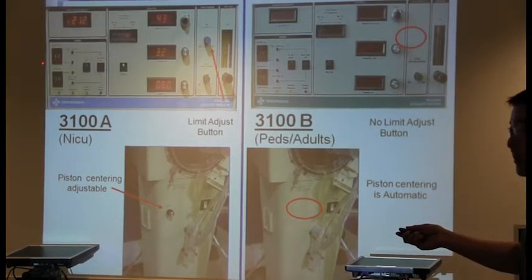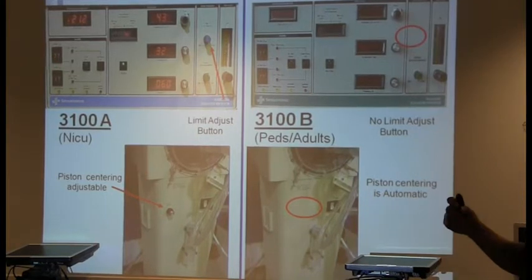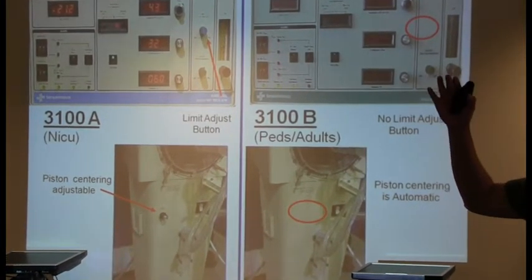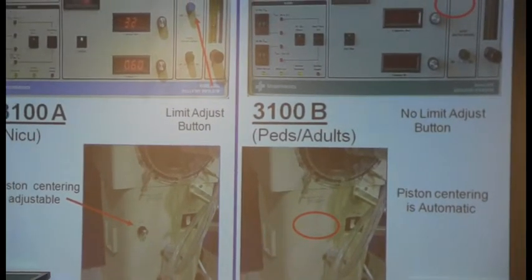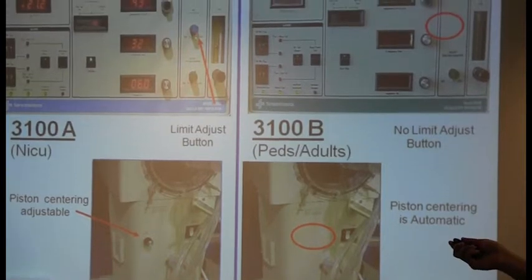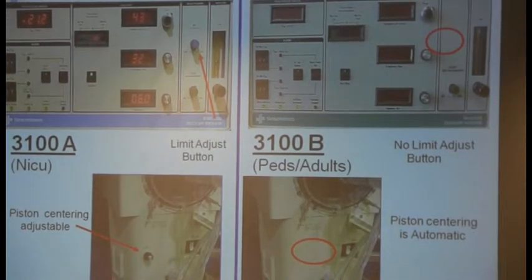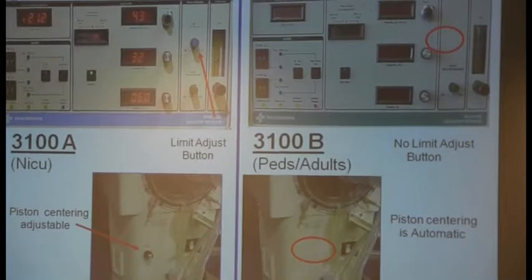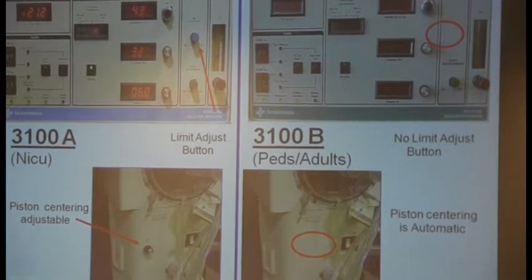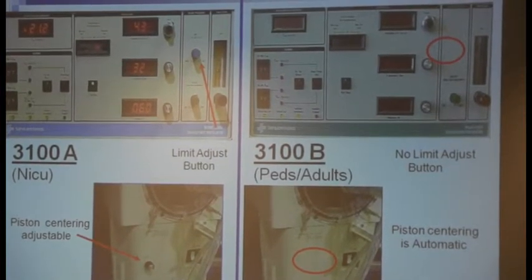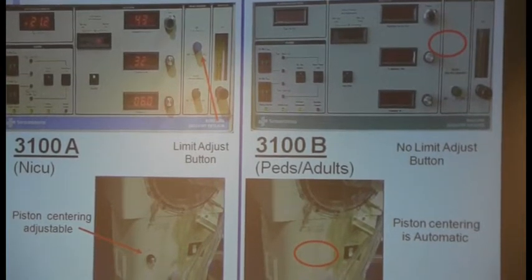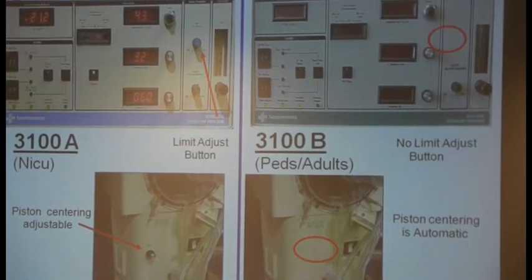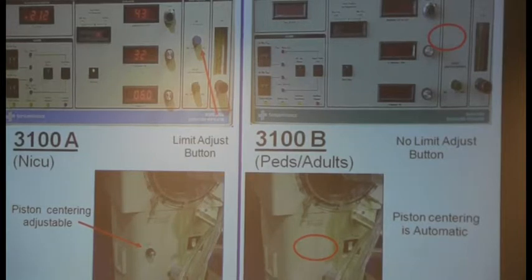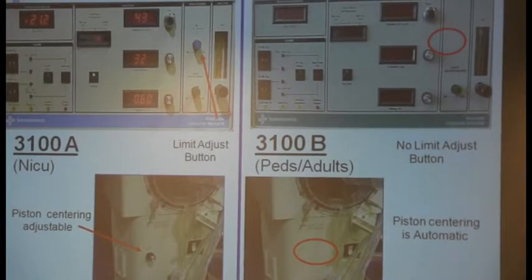Your max pressure over here is only an alarm. It tells you, hey, guess what? Whatever you set, it hit it. But the vent will still continue to function normally. So that's why you have to set your mean pressure limit alarm. A lot of people set those alarms the same, and that's a pop-off. And if you don't set that blue one on top, on the A, correctly, you're going to stifle your amplitude and you're going to stifle your mean. So it's very important you learn how to set that top limit now.